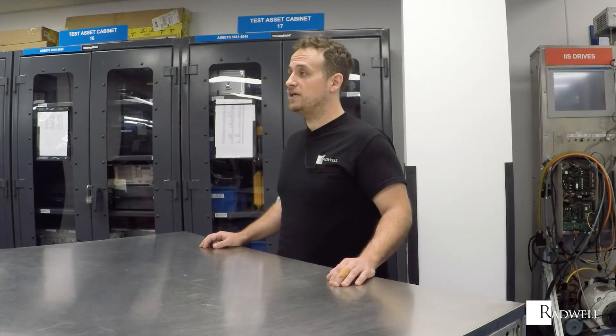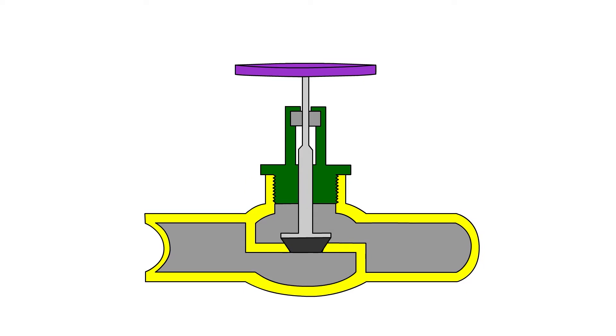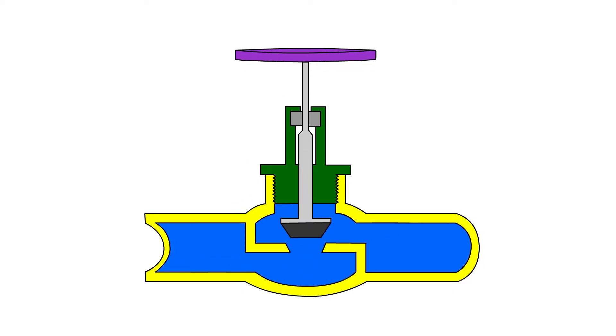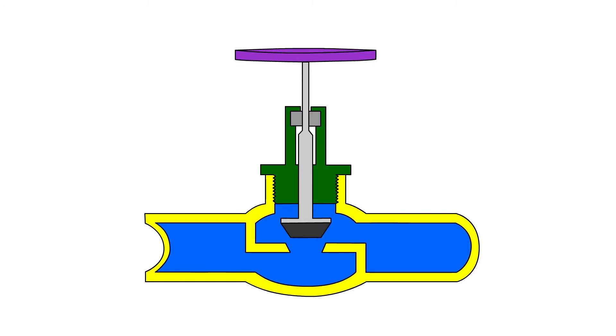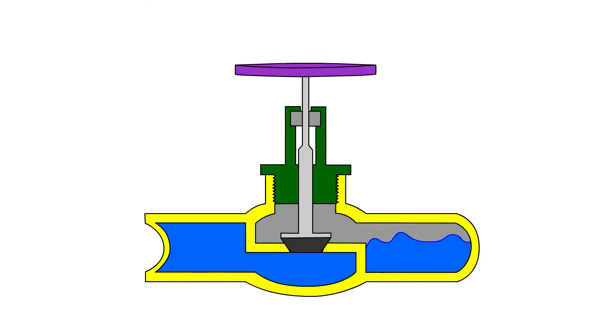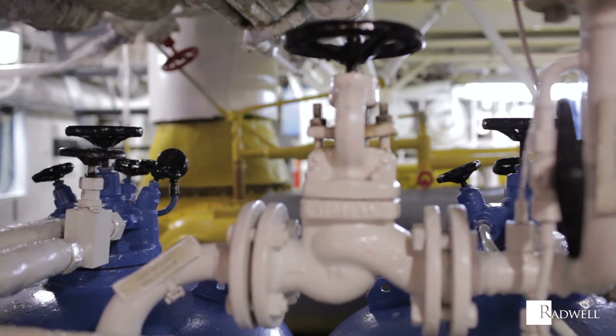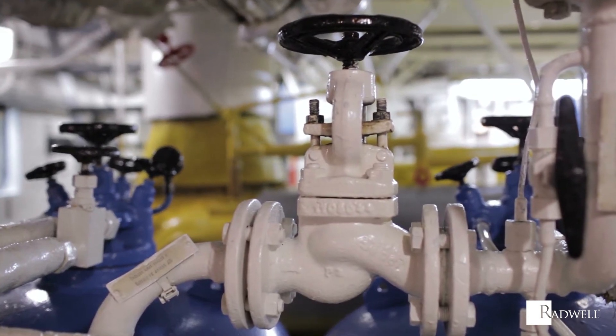A globe valve is a bit more advanced. It has the ability to stop, start, and regulate the amount of fluid flow. Like gate valves, globe valves operate by turning a hand wheel. This operation will raise or lower a cone-shaped plug out of the fluid flow pathway. The flow is controlled by how far away the plug is from the seat.